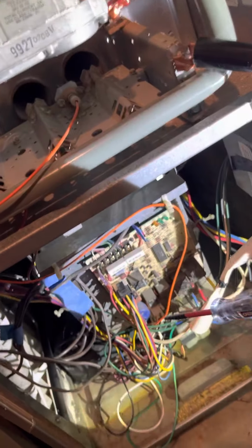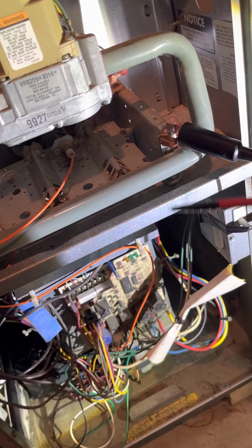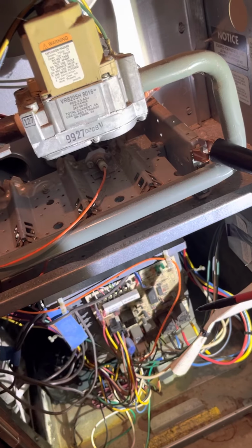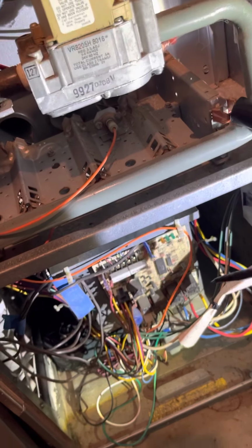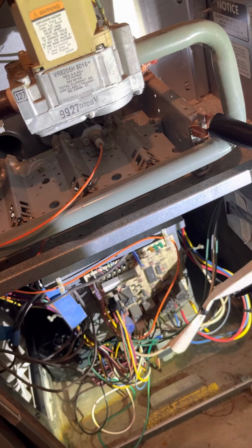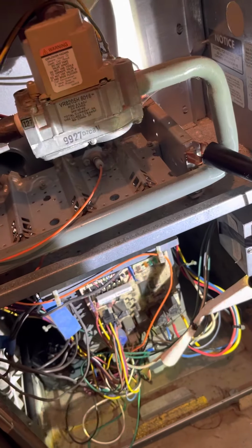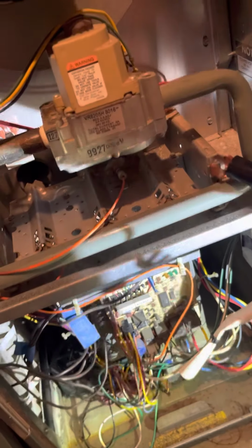You cannot touch 120 volts with the tester. So you have to know the difference between what the 24 volt control wiring is and the high voltage 120 volt wiring is. So make sure you know what you're doing before you go sticking a tester in there.